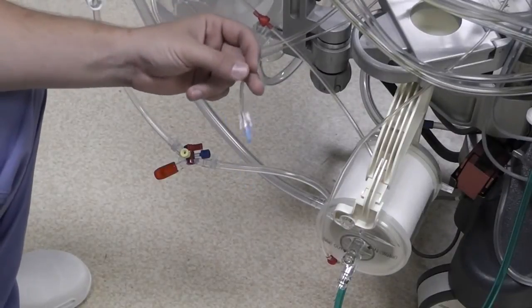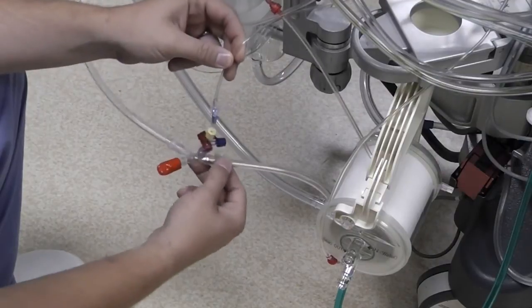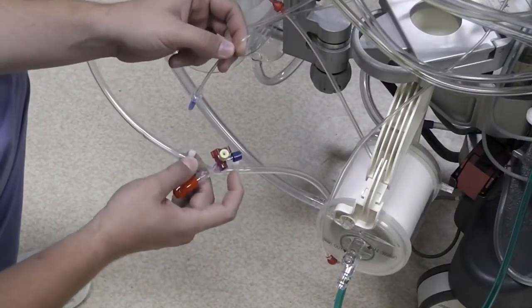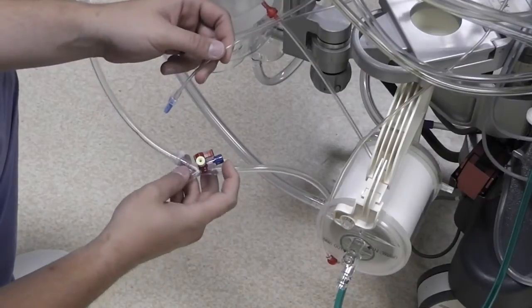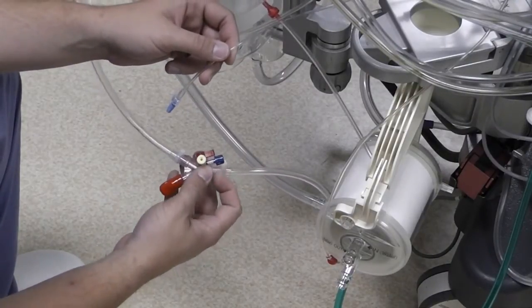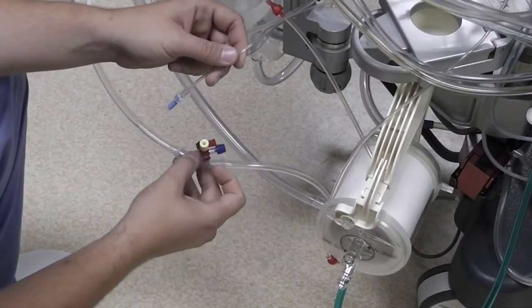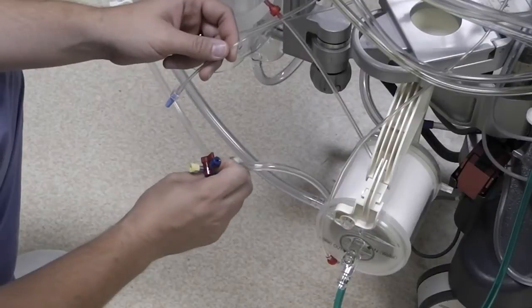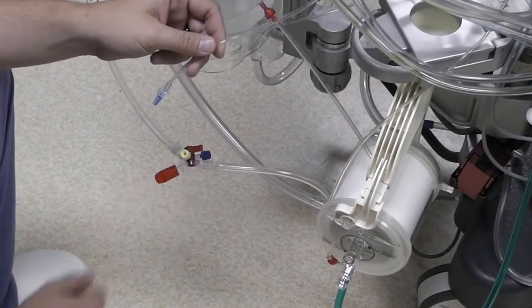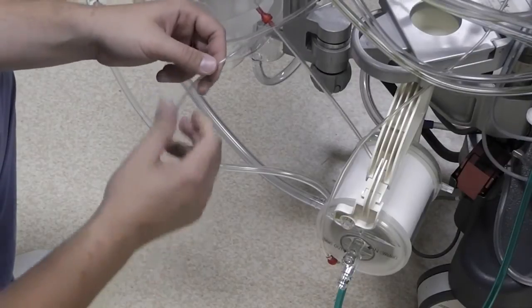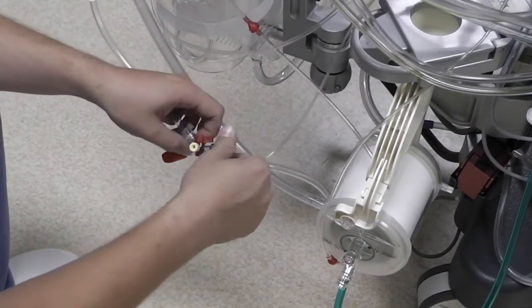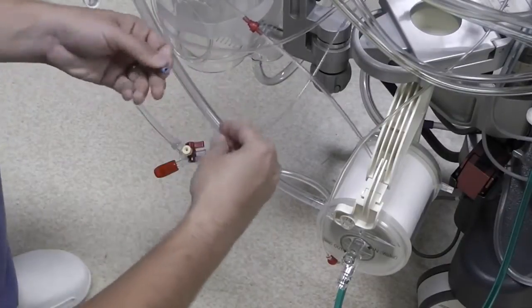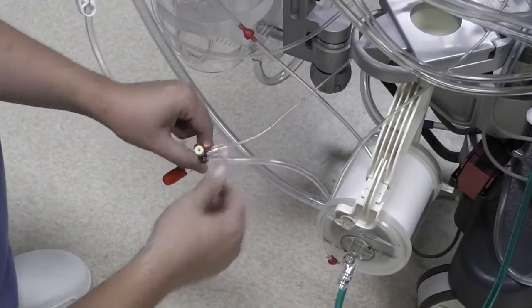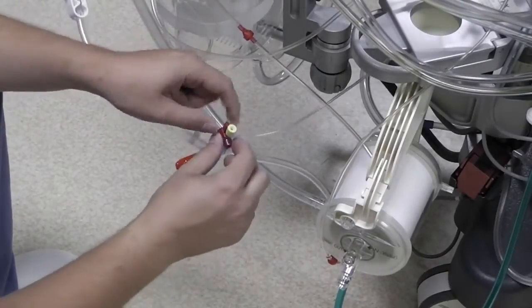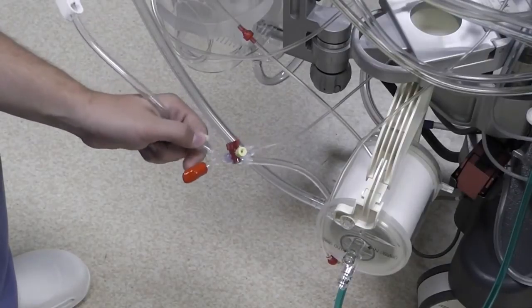This is the end of the line coming off that pressure bulb, and you will notice here on the recirculation line that there is a stopcock here, and there are 2 caps on it. One is blue and one is yellow. The yellow cap is a closed cap. Fluid will not flow through that. This blue cap is actually an open cap. If we were to fill this up, we would get fluid coming out of that. And obviously we don't want anything leaking out, so we're going to make a connection to that cap. And then just rotate this stopcock up to the yellow position just to close that off. You shouldn't get any flow out of there, but just to be safe, rotate that up.